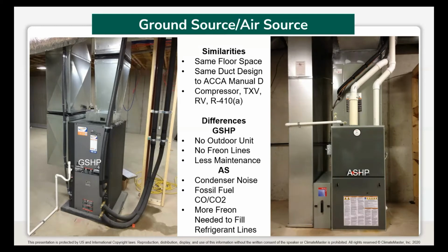We are eliminating outdoor condenser fan noise and compressor noise. We are eliminating a fossil fuel. Therefore, we are eliminating carbon monoxide and carbon dioxide production. We use far less freon in a packaged ground source heat pump because we don't have to fill refrigerant lines with refrigerant. So we have ounces of freon in our system as opposed to potentially 8, 10, 12 pounds of refrigerant.